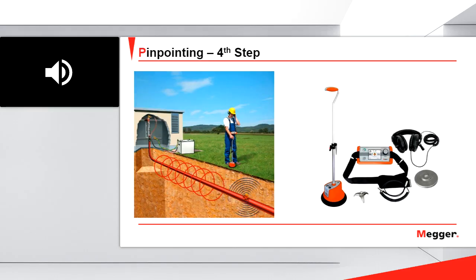In this step, I will have my thumper send high voltage pulses, let's say every 10 seconds. When the high voltage pulse arrives at the fault, I will have a flashover, I will have an arc, and the arc will generate first an electromagnetic signal and then an acoustic signal. Both signals will travel back to the thumper. The first one to arrive will be the electromagnetic signal, because it travels at the speed of light. The second one will be the acoustic signal, which travels at the speed of sound.